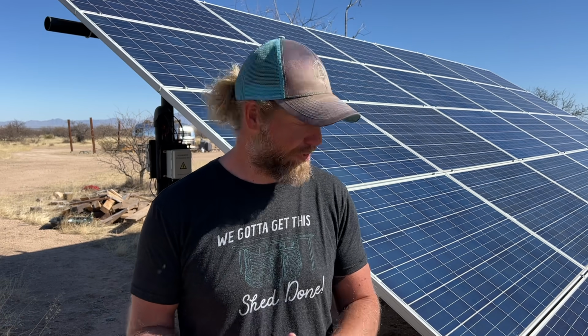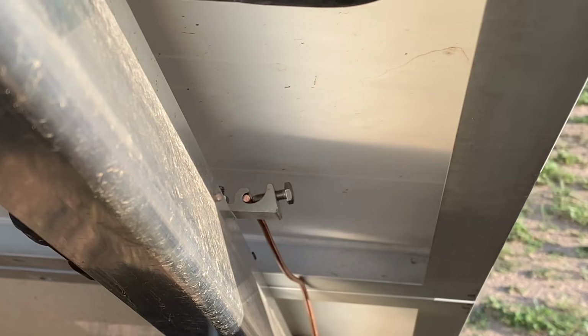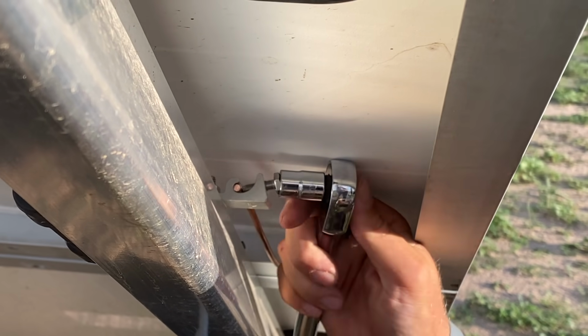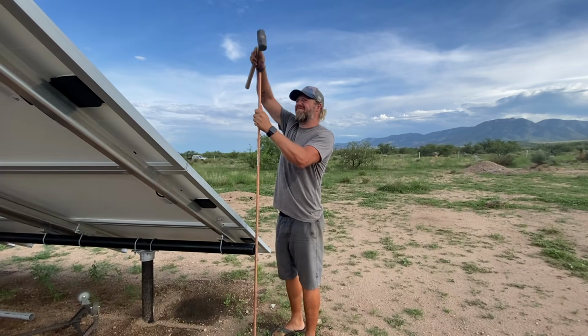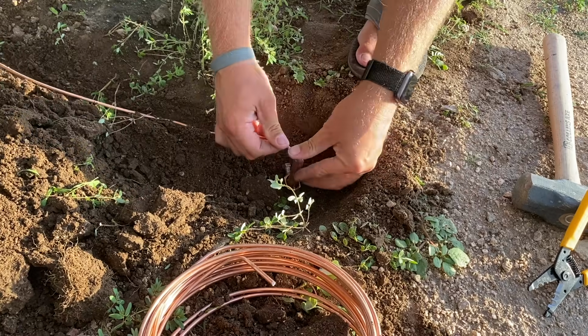Now, one last cool thing about this IronRidge system is grounding. Grounding's very important. You're putting a ton of power through this system. So the neat thing is that the way the IronRidge ground mount is designed is that all the metal is all touching each other. So the system is grounded by itself. But they also give you a grounding lug connection that connects to the frame, and you run a bare copper wire to an 8-foot ground rod.